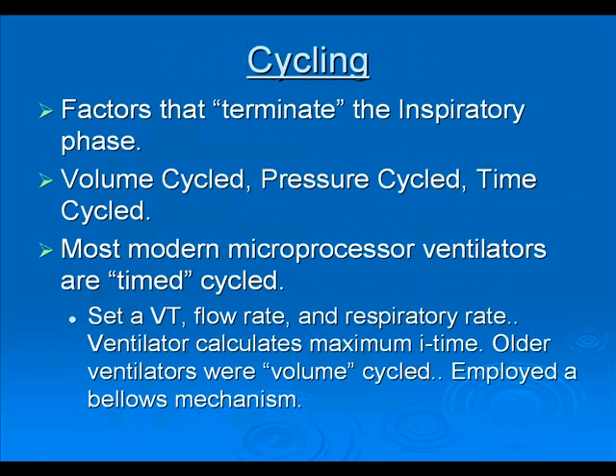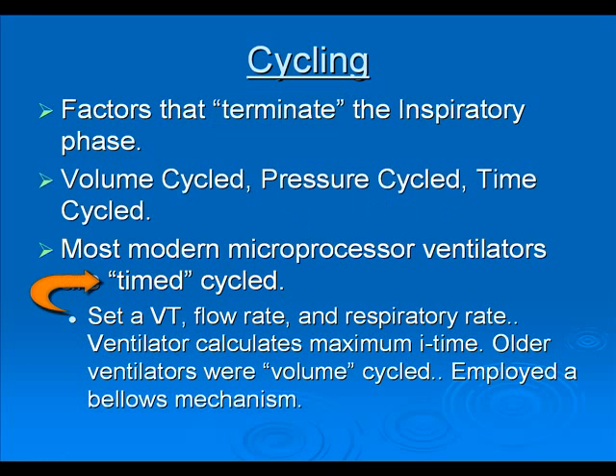When we refer to cycling, we're talking about which factor actually terminates the inspiratory phase. You can have a variety of different factors that end inspiration — volume cycle, pressure cycle, or time cycle. Most modern microprocessor ventilators are time-cycled: we set a volume, a flow rate, and a respiratory rate, and the microprocessor calculates the maximum inspiratory time to deliver those parameters. Older ventilators like the MA1 were truly volume-cycled and employed a bellows mechanism.